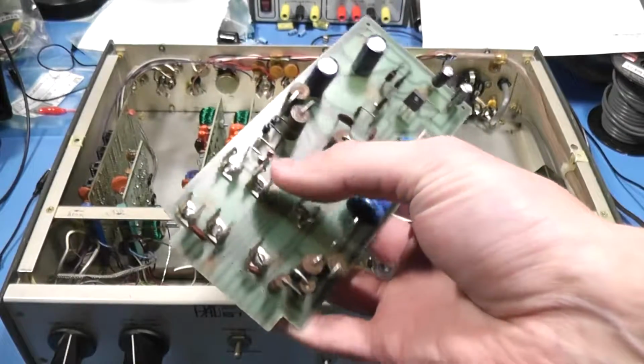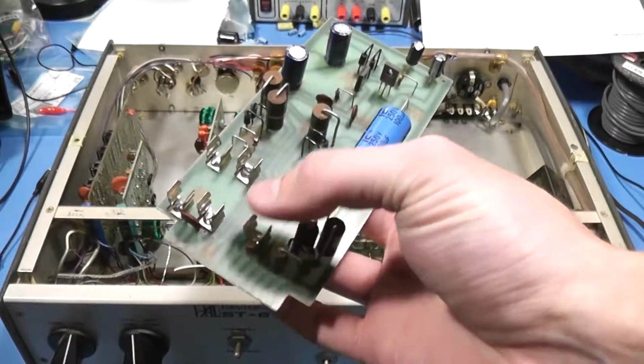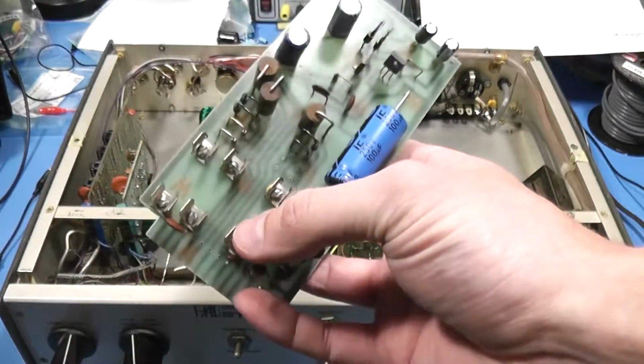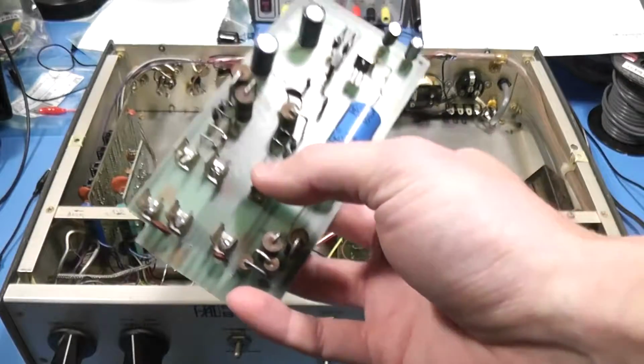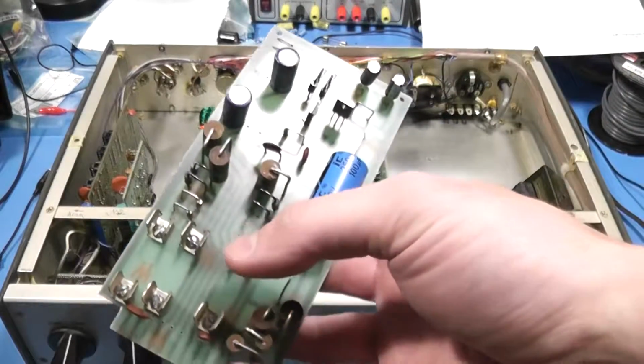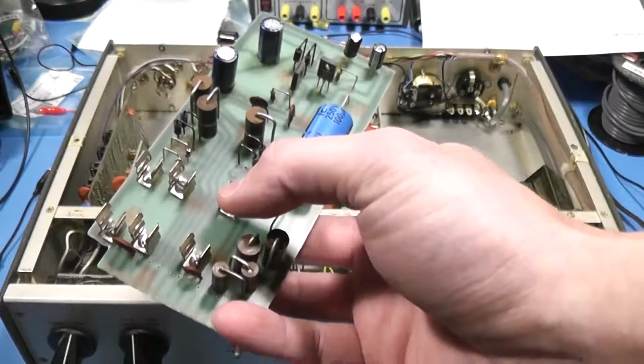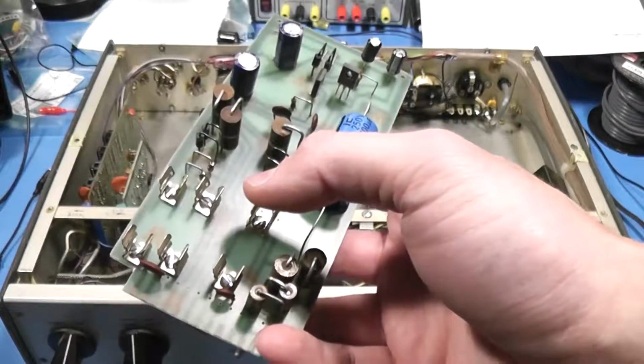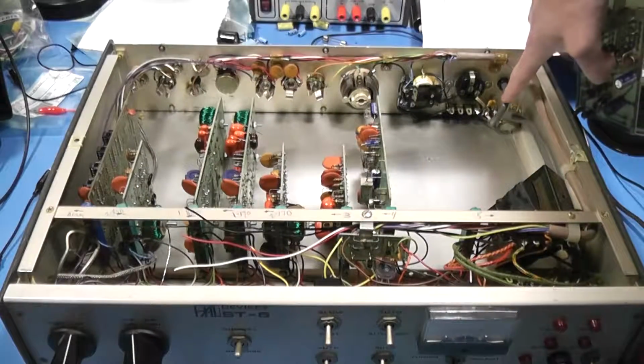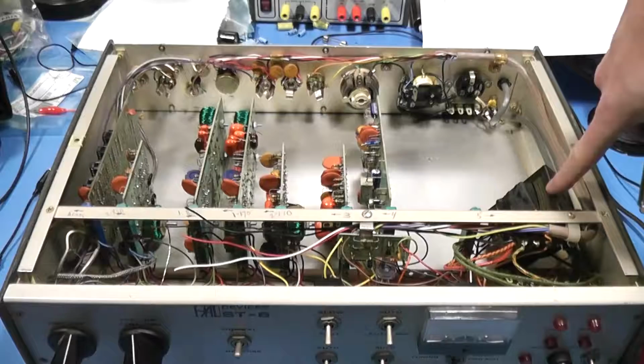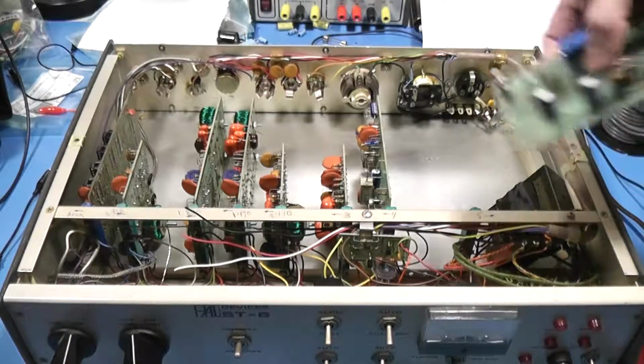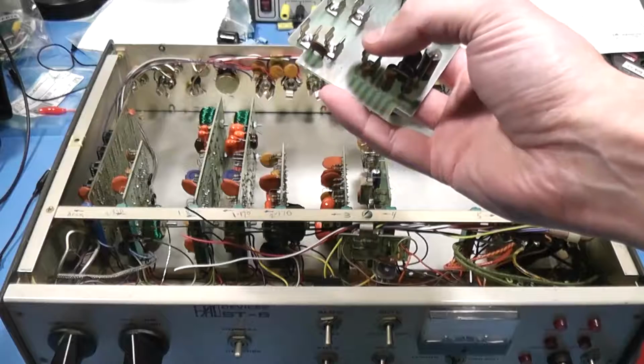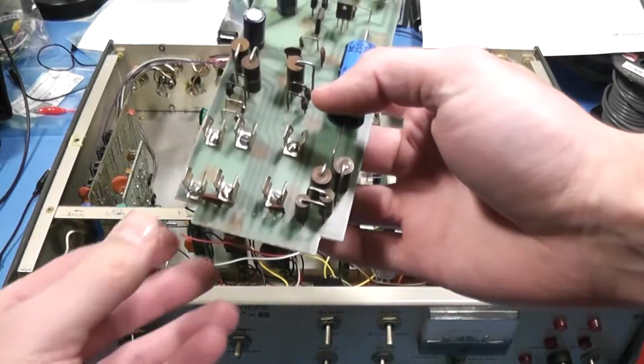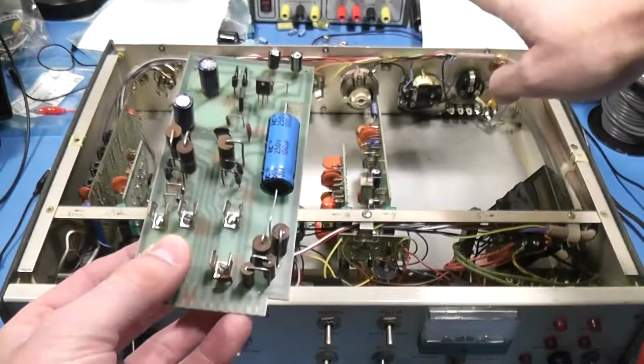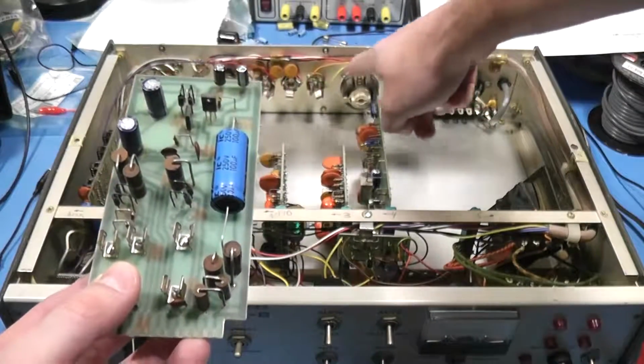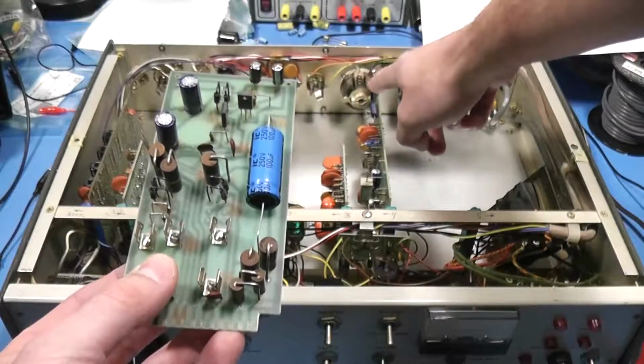If you see here, there are no fuses in this board - there are no fuses in this position. This is where the current loop fuse goes. And while I've been working on this, except when I was checking the current loop, I've been leaving this fuse out, which limits the high voltage in this supply to the primary side of the transformer here with the 120 volt line voltage and to the wiring leading to the input to this fuse, but there is no additional high voltage anywhere past that in this chassis, in particular not on these upper exposed terminals on this potentiometer on the back.